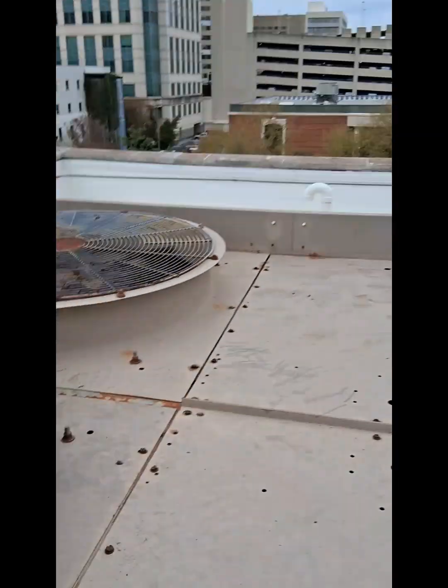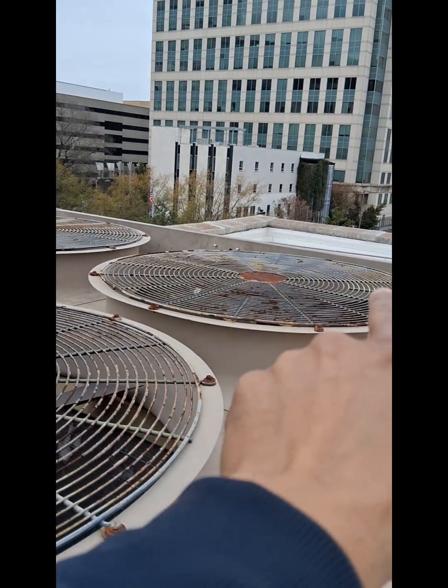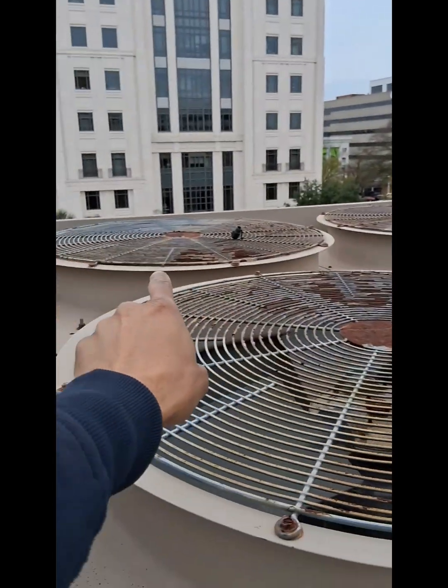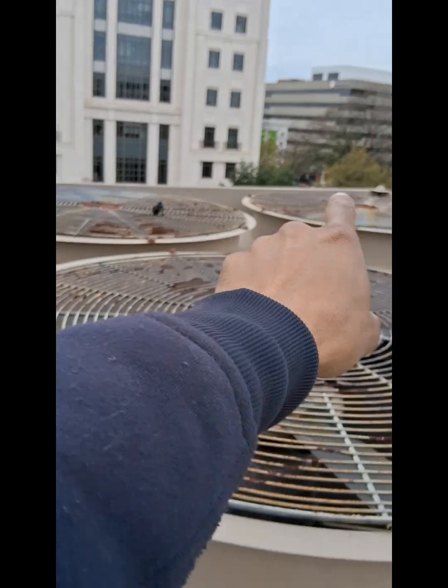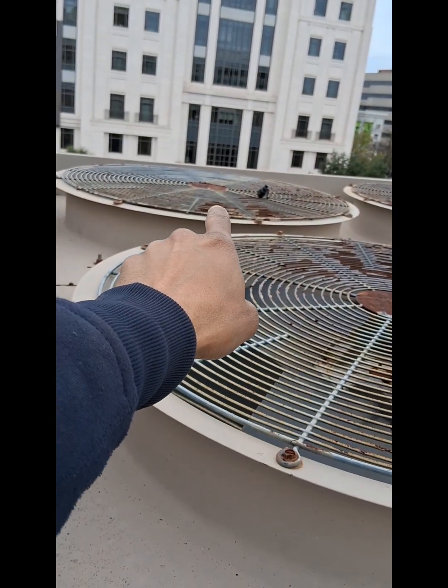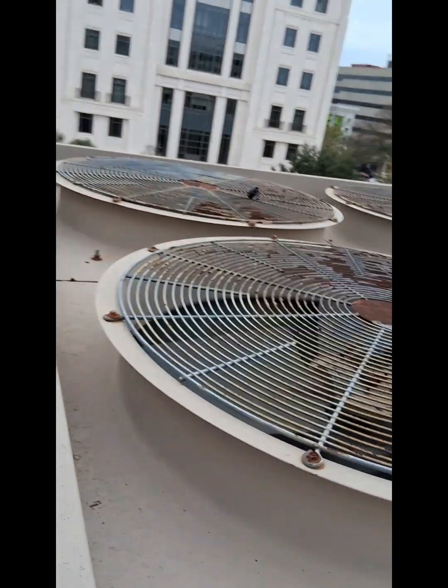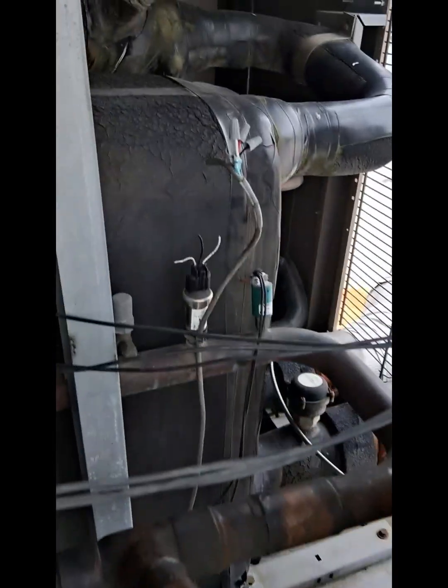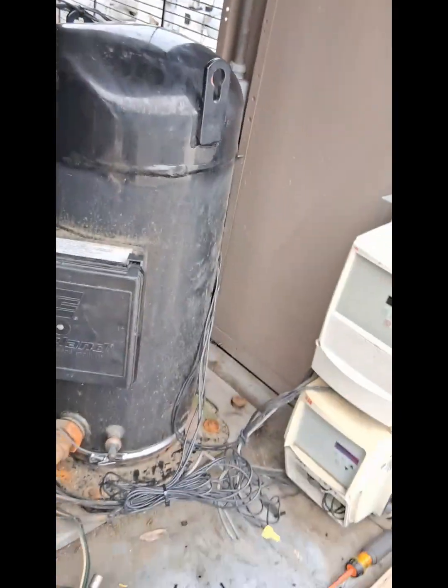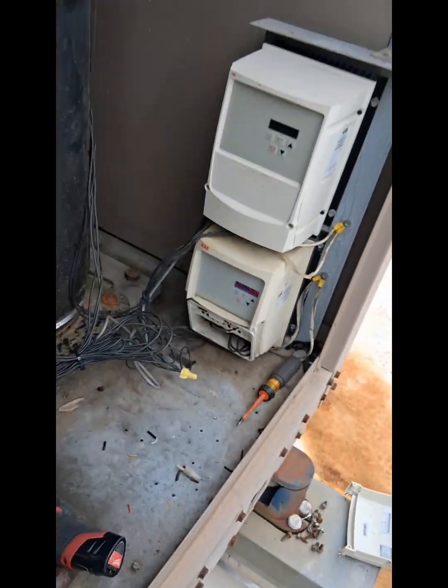And then here's the motor. It's the one right here. I already replaced that motor and put it over there because I got a bad discharge pressure transducer on this circuit 1 right there. But I'm about to go to my next job.